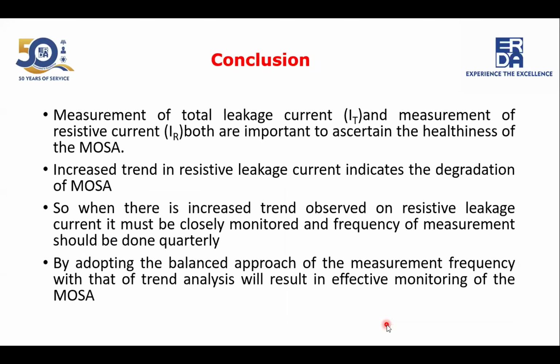So the conclusion is that measurement of total leakage current, IT, and measurement of resistive leakage current, IR, derived from the third harmonic resistive component, are very important parameters to decide the healthiness of the surge arrestor. An increasing trend in the resistive leakage current indicates degradation of the MOSA, and if timely action is not taken on a degraded MOSA, it may lead to a fatal accident or system failure.